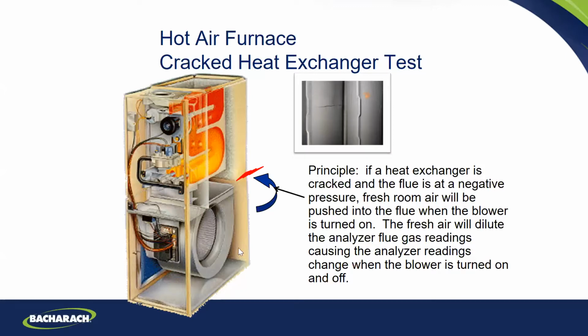Okay, then you turn your air handler on, and it makes that differential pressure, and your oxygen goes up by 0.5% or more, which is probably getting it through that crack. So if it went from 6 and went up to 6.5 or more, it's indicative of a crack, and it shows you should probably do further investigation.